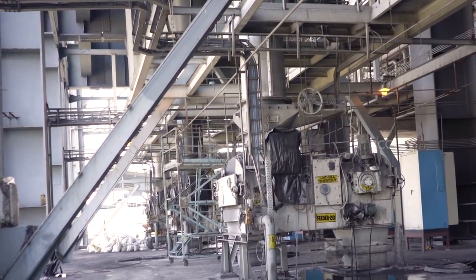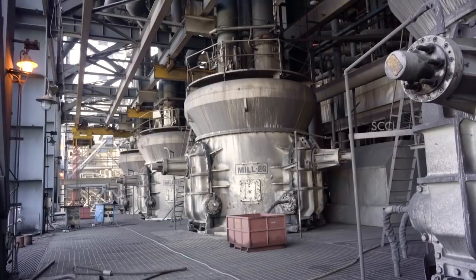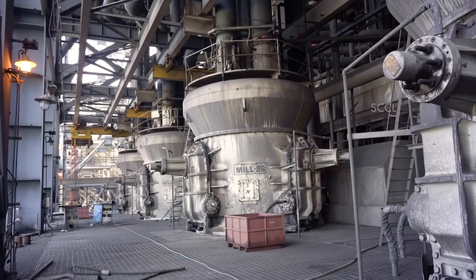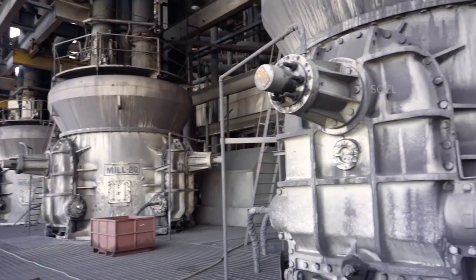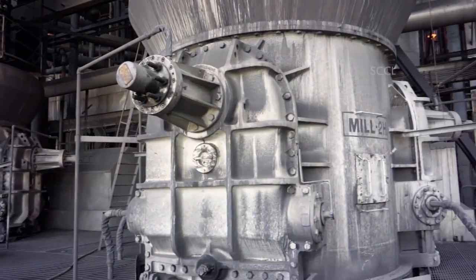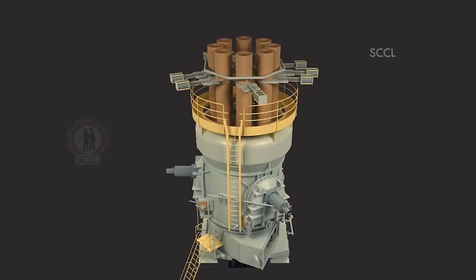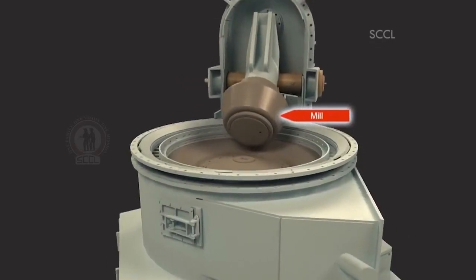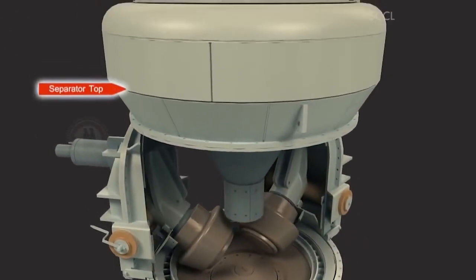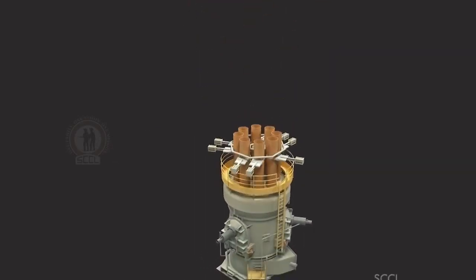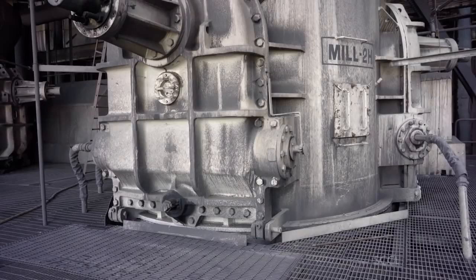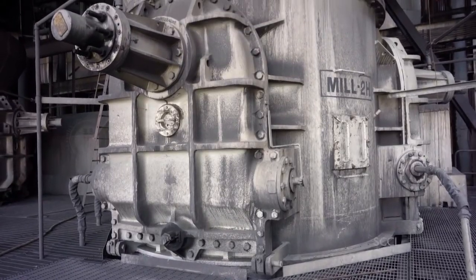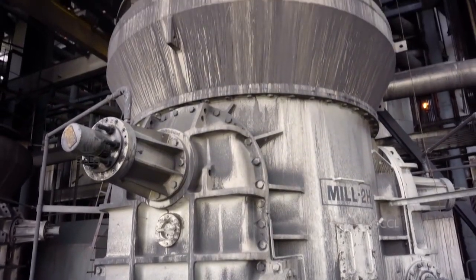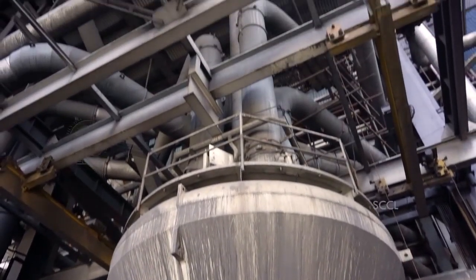The coal is then measured and is moved to the bowl mills. These bowl mills have 3 rollers attached to a vertical shaft, and crushed coal from the crusher house is pulverized up to 40 to 70 microns in size, which appears to be like a fine powder. Now the finely powdered coal leaves the mills and heads to the boiler. About 70 tons of coal can be pulverized per mill per hour.